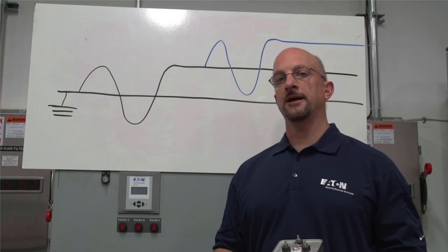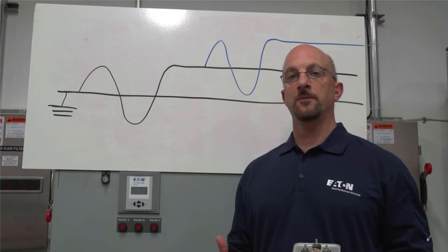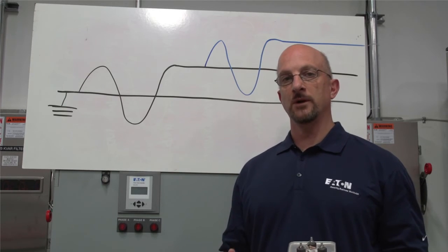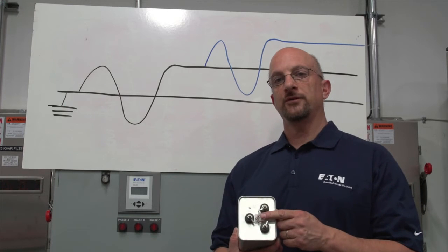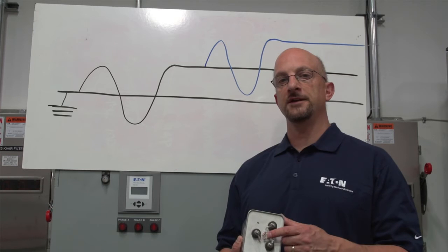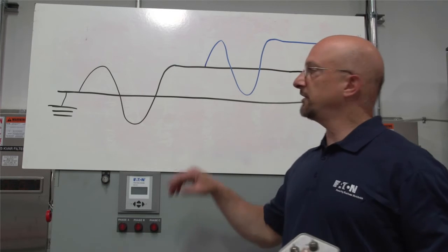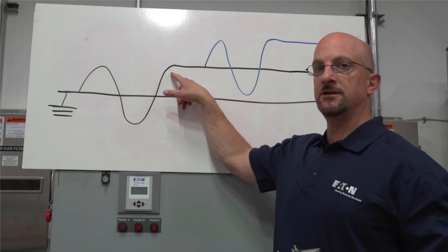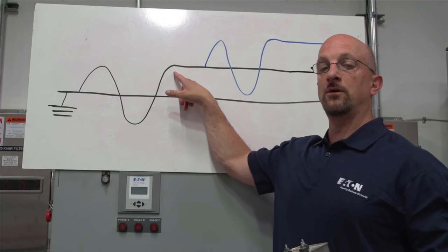The power system is a lot like that. In fact, the power system is very capacitive in that sense if it's ungrounded. On a power factor correction capacitor, we put resistors to bleed off the DC trapped charge. So if we have a ground fault here in the power system and we take away the ground fault, or if we have a ground fault in an ungrounded power system and we take away the AC voltage...